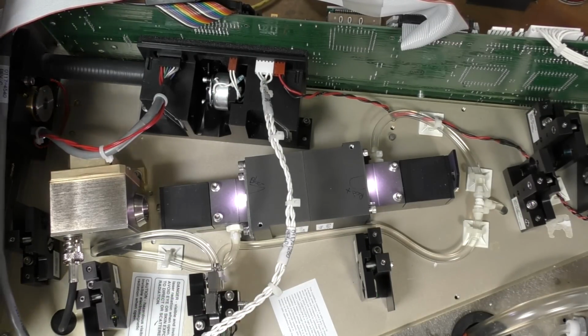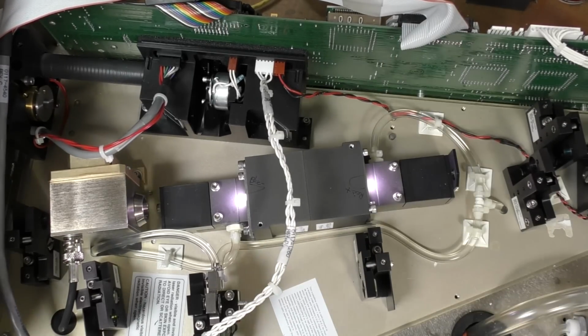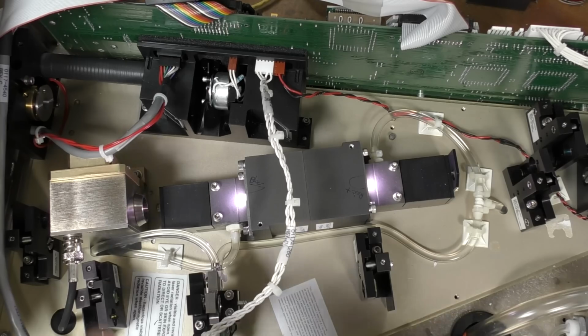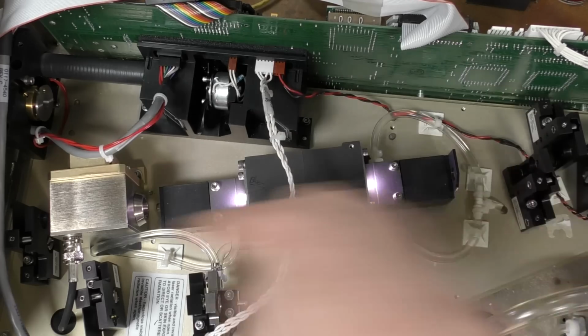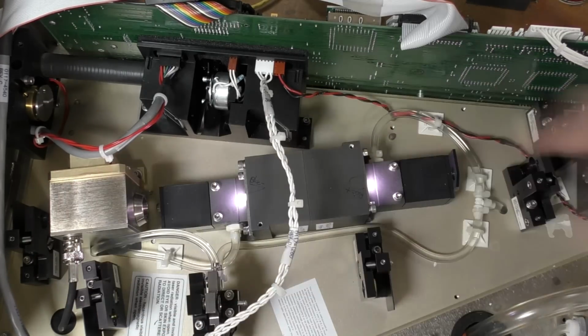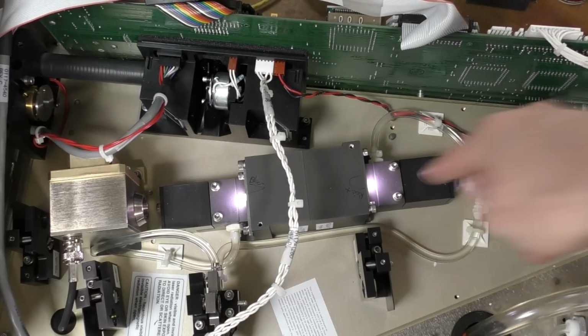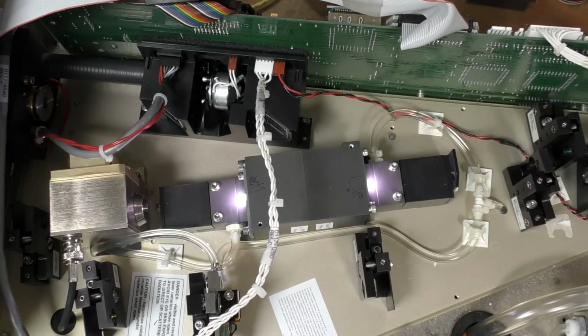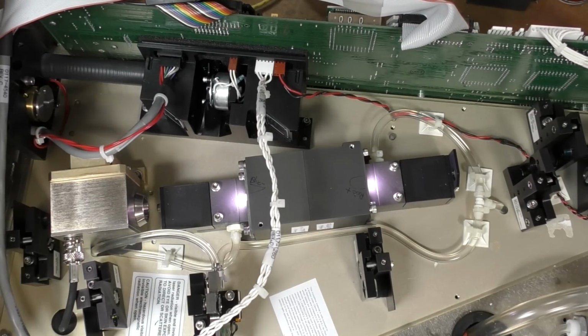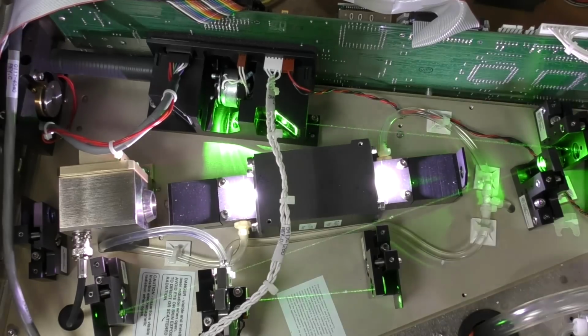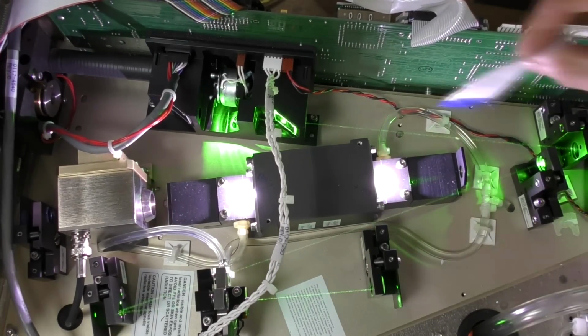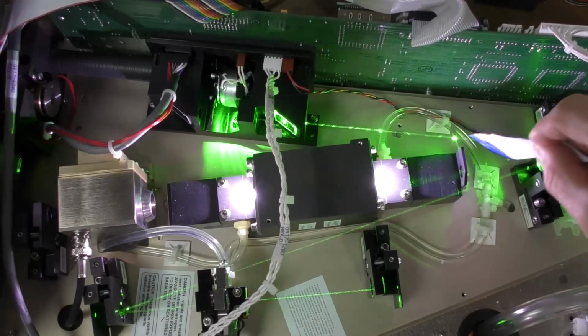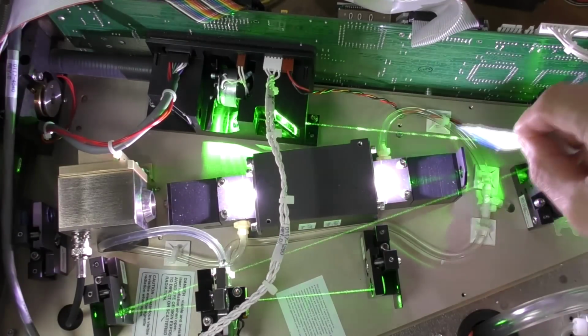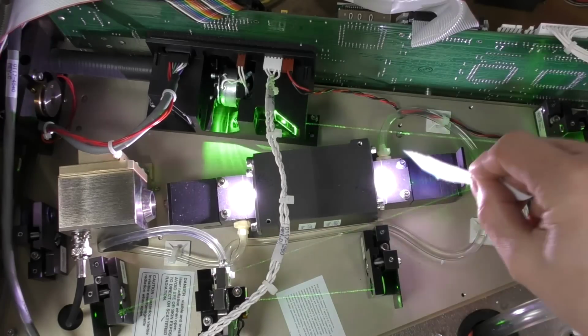So with a bit of smoke you can actually see the beam path. Interestingly, we didn't see anything at all going through the laser cavity, so obviously we've got the frequency doubled, 532 nanometers path going through here, and it's only going to be the infrared 1064 going through the actual cavity, which is interesting. Draws about 400 watts in this sort of standby mode. It pulls about 1400 watts when it's going at full power. Let's see if we block that beam, the green disappears, so we just can't see it because it's infrared.